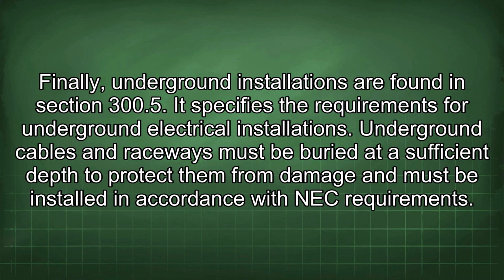Finally, underground installations are found in Section 300.5. It specifies the requirements for underground electrical installations. Underground cables and raceways must be buried at a sufficient depth to protect them from damage and must be installed in accordance with NEC requirements.